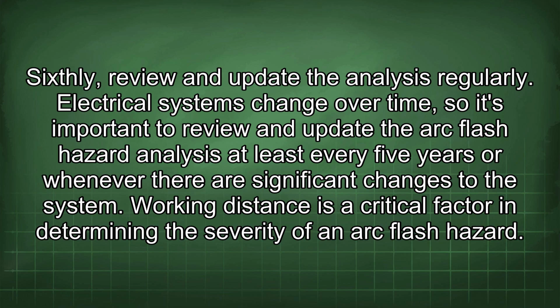Sixthly, review and update the analysis regularly. Electrical systems change over time, so it's important to review and update the arc flash hazard analysis at least every 5 years or whenever there are significant changes to the system.